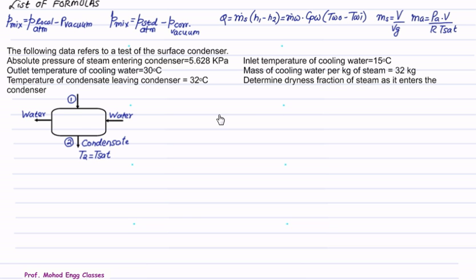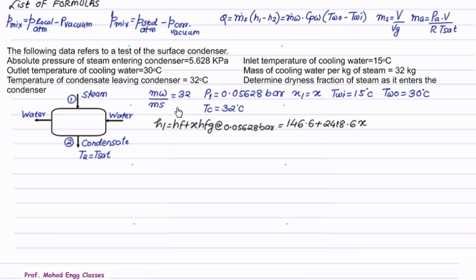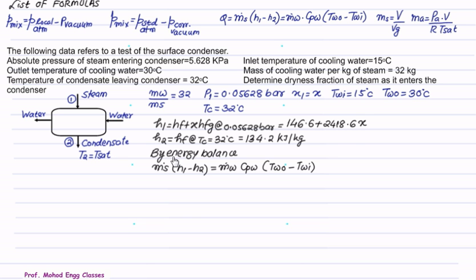We want to find the dryness fraction of steam as it enters the condenser. The ratio of mass of water to mass of steam is 32. P1 is 0.05628 bar and X1 is unknown, so let it be X. Inlet water temperature is 15°C and outlet is 30°C. We calculate H1 as wet steam: HF + X·HFG at 0.05628 bar, which from the steam table is approximately 146.6 + 2418.6·X. H2 at condensate temperature of 32°C gives HF = 134.2 kJ/kg from the steam table.